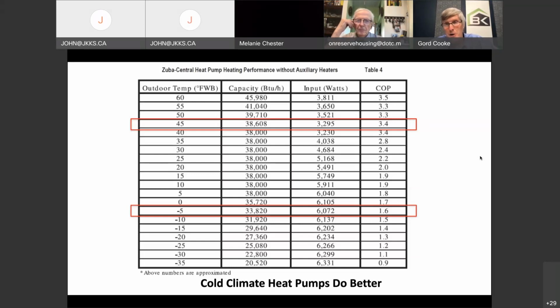On the far right is its coefficient of performance. Notice at 45 degrees, it's 3.4 times. That is, for every dollar of electricity, you get $3.40 worth of heat. When it gets to -5, now it's only 1.6 times efficiency. And in fact, its efficiency drops to around 1. That is, for every dollar you spend, you're getting $1 worth of heat.